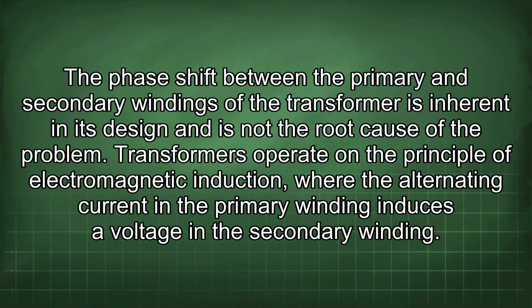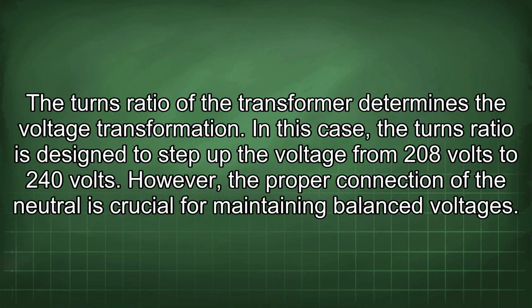The phase shift between the primary and secondary windings of the transformer is inherent in its design and is not the root cause of the problem. Transformers operate on the principle of electromagnetic induction, where the alternating current in the primary winding induces a voltage in the secondary winding. The turns ratio of the transformer determines the voltage transformation. In this case, the turns ratio is designed to step up the voltage from 208 volts to 240 volts. However, the proper connection of the neutral is crucial for maintaining balanced voltages.